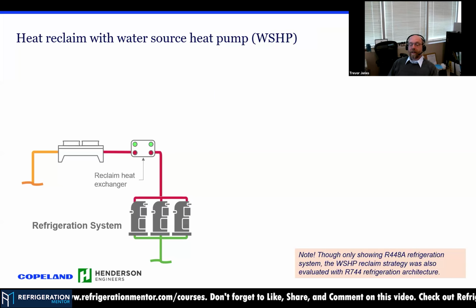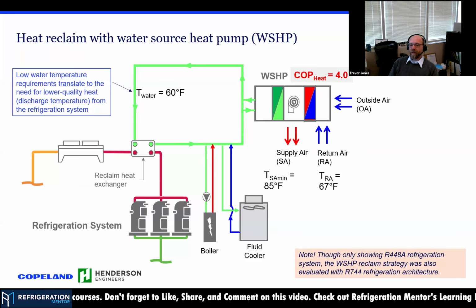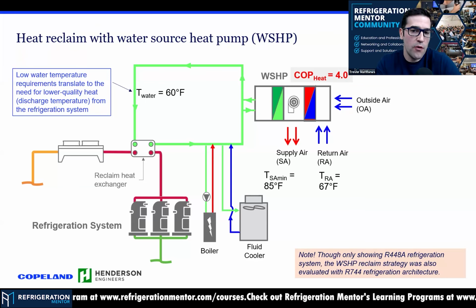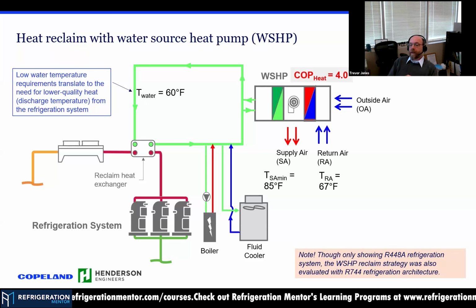So adding water source heat, or heat reclaim, to the water source heat pump reclaim heat exchanger, we're looking at a loop temperature of roughly 60 degrees, which keeps the condensing temperature of CO2, or the refrigerant, low, basically at minimum. The efficiencies of the water source heat pump at that range are roughly 4, you can get a little bit better, but that was a nice round number. And this right now is talking about the 448 system, correct? We actually looked at it for both the 448 and our CO2, 744, system. Okay, so yeah, this is what the system was looking like.